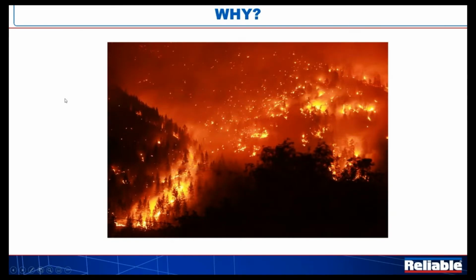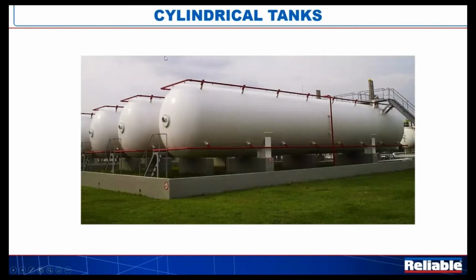So here you can see we have a wildfire. Well, what does water spray have to do with the wildfire? Well, out in the middle of that wildfire, in the line of fire, if you'll pardon the pun, we may have things like this. Now, generally in a large industrial site, there's going to be setbacks and clearings and things like that to prevent that onrush of fire from creating havoc with this type of asset. But occasionally we do need to do something additional. So in this case, we're looking at not necessarily an issue that might arise within the tank setup itself, but more on what's going to happen when that fire rolls into our environment.